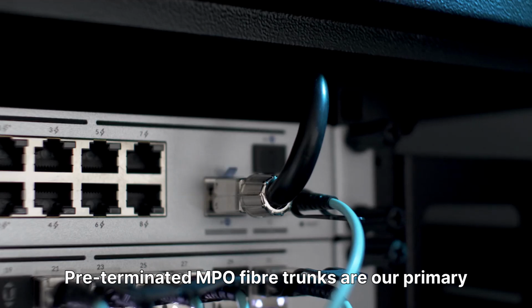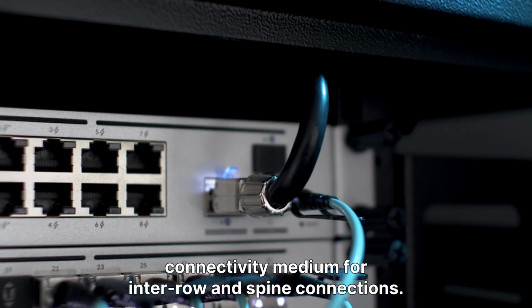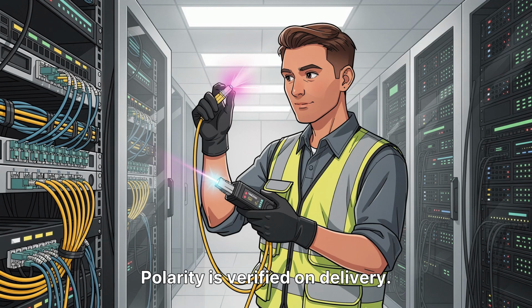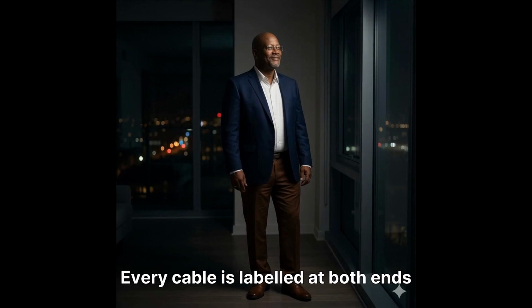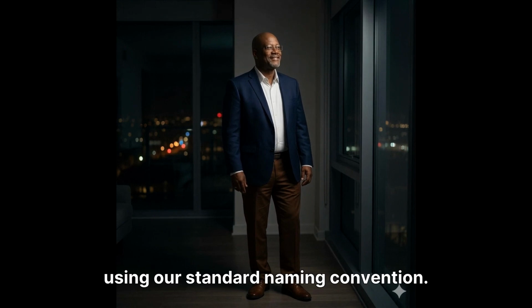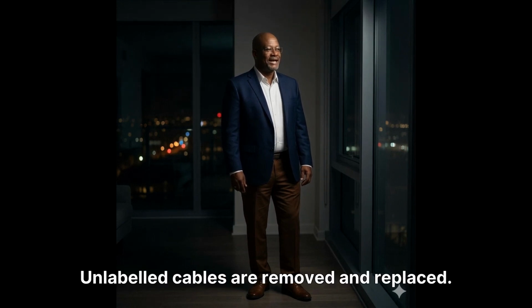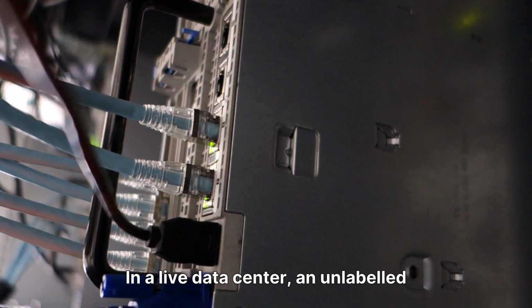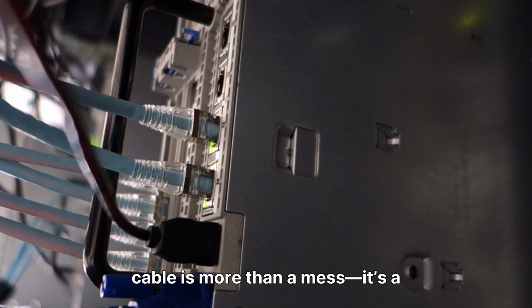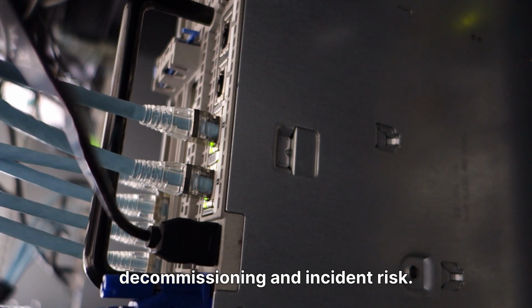Pre-terminated MPO fiber trunks are our primary connectivity medium for inter-row and spine connections. Polarity is verified on delivery. Correcting an error on a 144 fiber trunk later takes hours of rework. Every cable is labeled at both ends using our standard naming convention. Unlabeled cables are removed and replaced. In a live data center, an unlabeled cable is more than a mess. It's a decommissioning and incident risk.